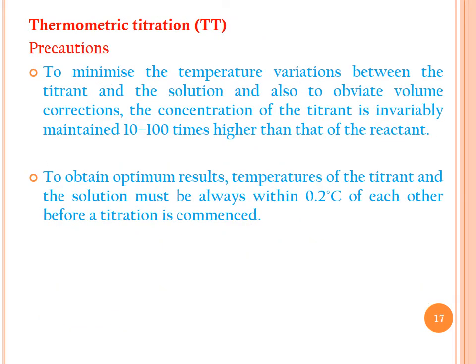During thermometric titration, as a precaution, the concentration of the titrant is invariably maintained 10 to 100 times higher than that of the reactant to minimize temperature variation and obviate volume correction. To obtain optimum results, the temperature of the titrant and the solution must be within 0.2°C of each other before a titration is commenced.